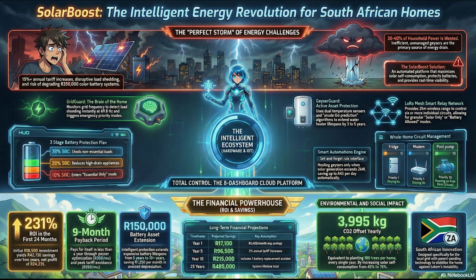During a critical grid crisis, when the 50 Hz frequency starts to drag dangerously low, Eskom doesn't initiate rolling blackouts. Instead, the VPP sends a secure, instantaneous, encrypted signal to the master controllers in 50,000 connected homes. And what do they do? The grid guards instantly actuate the relays, and 50,000 3-kilowatt geysers and pool pumps turn off simultaneously for exactly 20 minutes. The system artificially and instantaneously removes hundreds of megawatts of strain from the national grid.